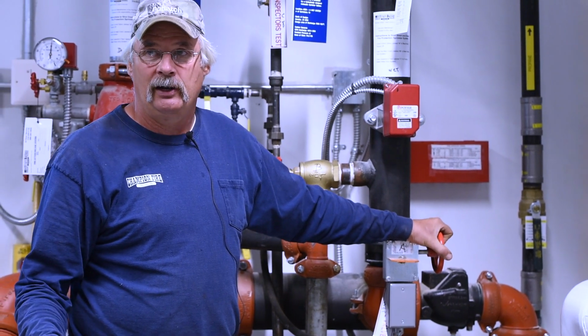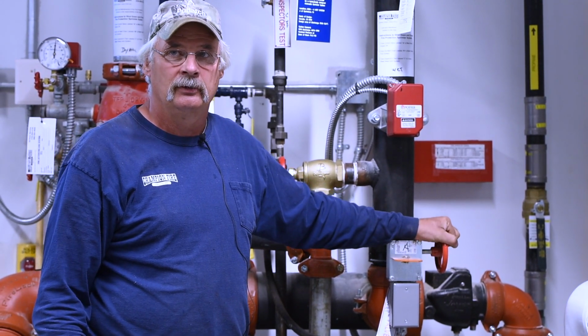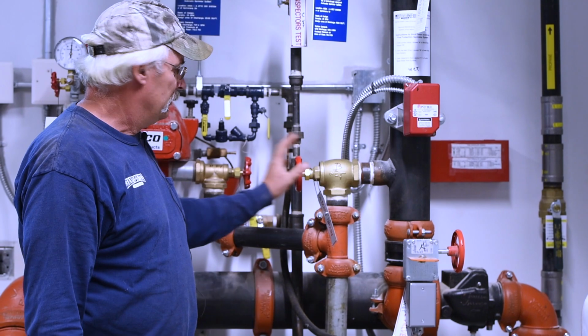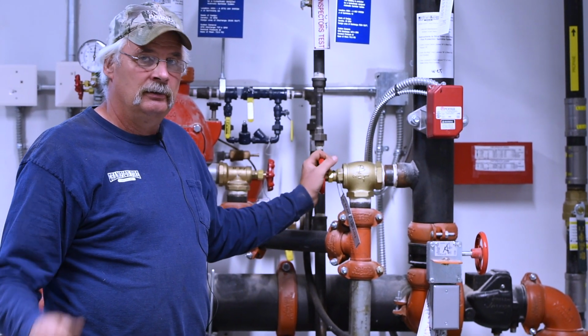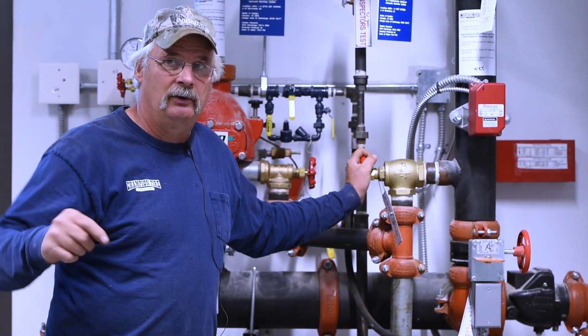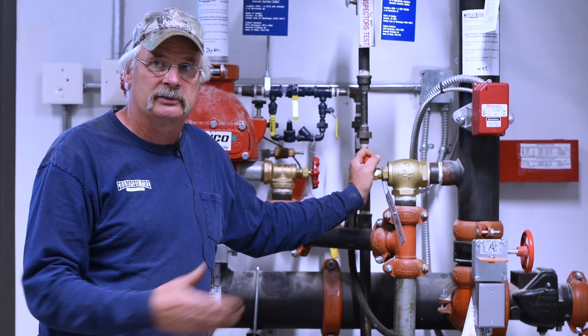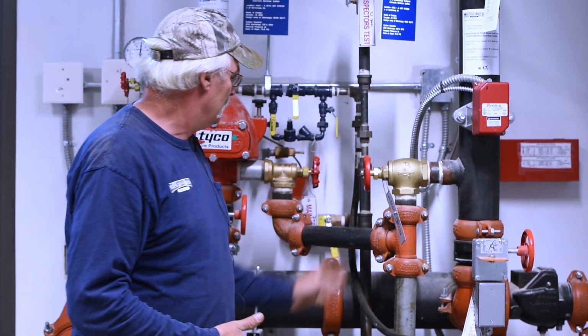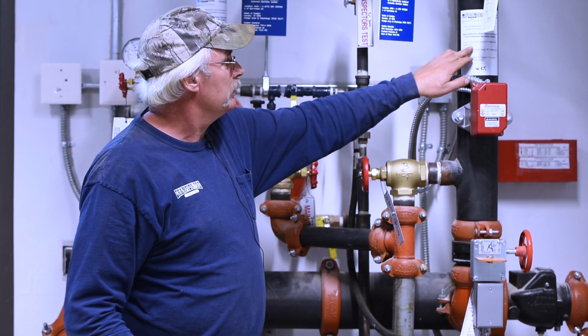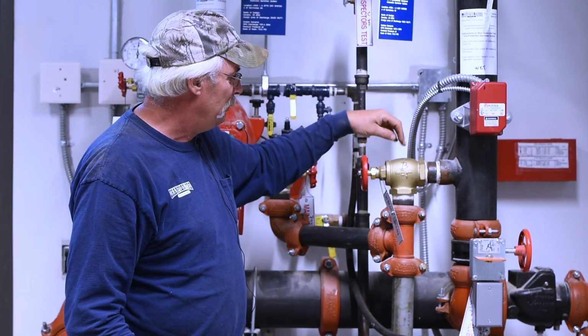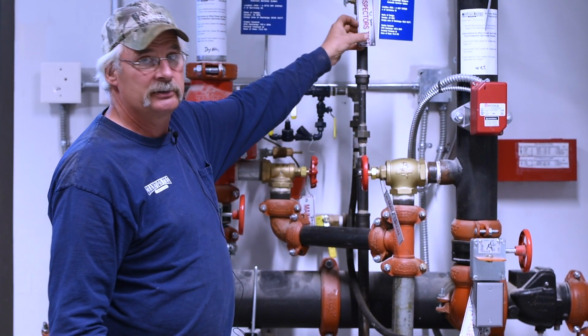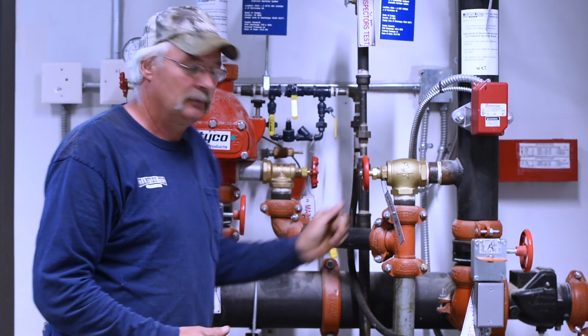What do we want to do if we've got water running? Shut it off. What else do we want to do? Drain it. The best thing to do is get the water down and out of the building, so all these drains are set up to get out of the building. Step one, close the control valve A. Step two, open main drain B. Step three, open inspector test C on this wet system.